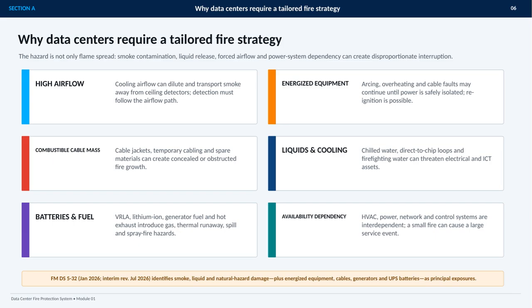High cooling airflow can dilute smoke and carry it away from ceiling detectors, so detection needs to account for airflow paths. Energized equipment may continue arcing or overheating until power is safely isolated and reignition remains possible. Combustible cable jackets, temporary cabling, and stored materials can support concealed fire growth. Liquids, including chilled water, direct-to-chip cooling fluids, and firefighting water, can damage electrical and information technology assets.